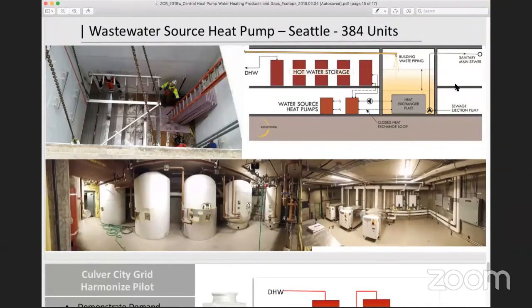So it's a gas cooler, and you're trying to cool down this gas as part of the thermodynamic cycle. And the colder that you make that water, as you're cooling it down with city water, transferring the heat out, the better positioning you give the heat pump on that next cycle is probably the way to explain it without having the chart in front of me.